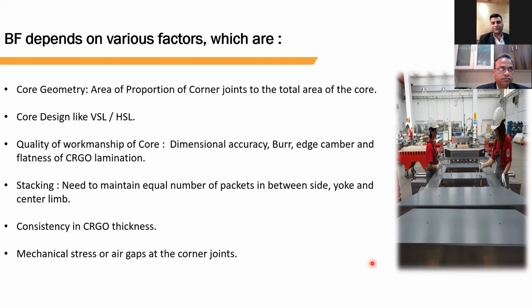We have seen designs where limb height is very high in proportion to yoke length, so the ratio of leg center to window height is different compared to normal design. If you increase your yoke length, the yoke portion increases, where maximum CRGO is placed. And if you reduce limb height, the side and center limb become short. This impacts building factor because you apply fewer turns while putting more weight in the top and bottom yoke.